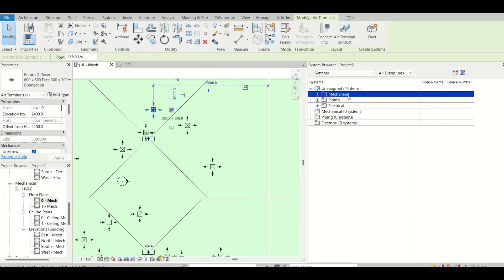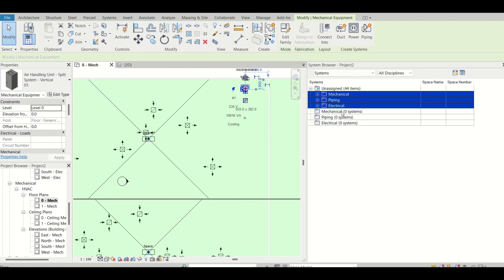If I click on Unassigned, each and every element will be visible under either mechanical, piping, or electrical — but in an unassigned category rather than a proper system. For example, if I select this air terminal it comes inside Mechanical. Why? Because each element has its connector. This return diffuser has a return air connector, and based on that connector it defines the air category.